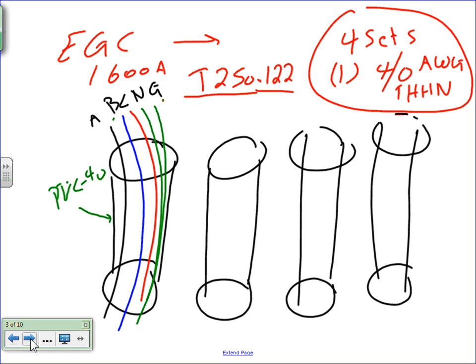When we went to Boston Scientific, I don't know if you guys paid attention to the grounding electrode system. They have a 500 kcmil conductor ring around the whole building, and they tied a ground rod every 100 feet or so, and that's typical in major buildings. So this is the bare minimum by code, but there's no conflict in that. But I see your point. No, it doesn't make sense. Yeah.